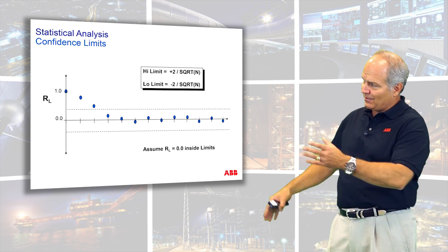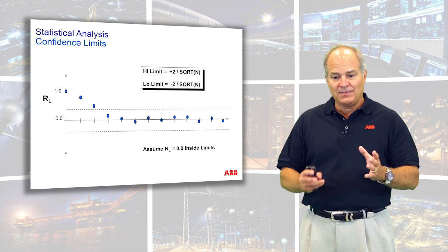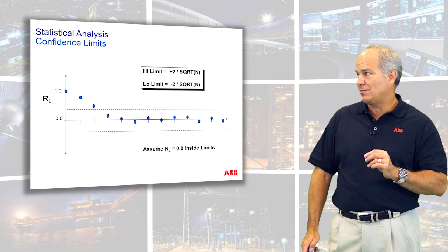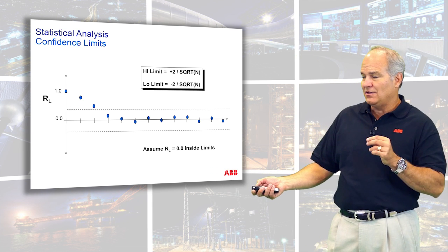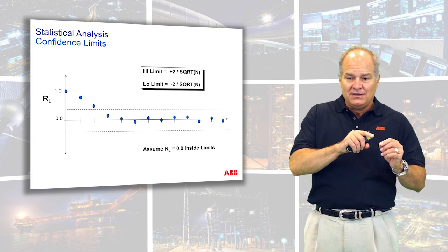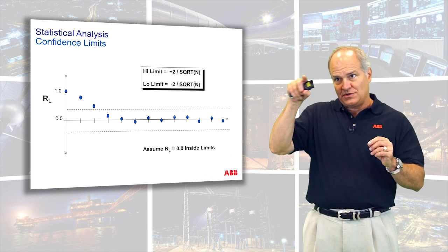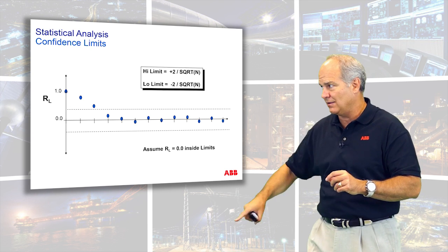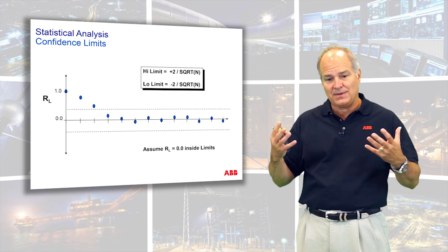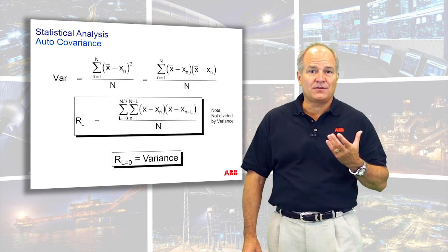That's what we're looking at here. So this one shows this shape, and roughly 3 to 4 shifts it went into the confidence limits. And then from there on, it's considered noise. So there's no useful information once it gets into the noise band. The trick with process control is to get it from a 1 to the noise as fast as you can without going unstable. And so if you can imagine a loop that's tuned very, very slow, it'll take a long time to get there. If it's tuned perfect, it'll shoot in very fast. And if it's tuned oscillatory, it'll oscillate. So by looking at the autocorrelation with a process control perspective, you can sort of see how aggressive the control loop is tuned.